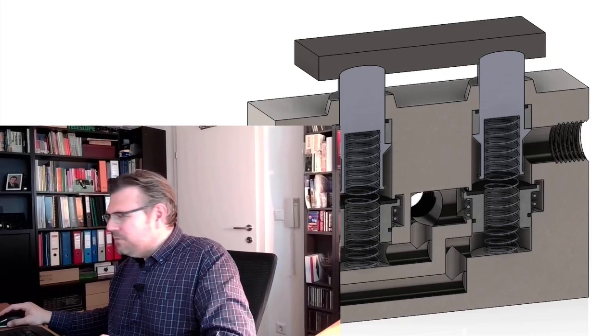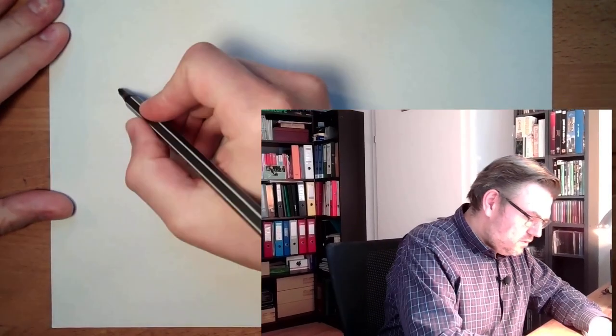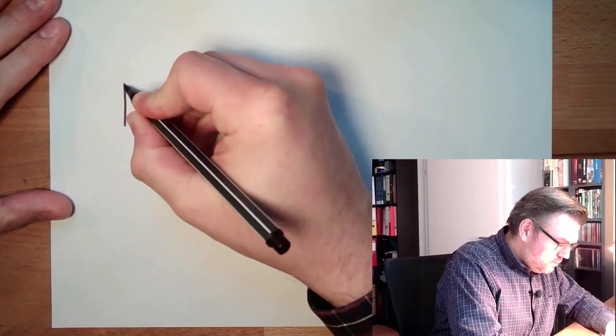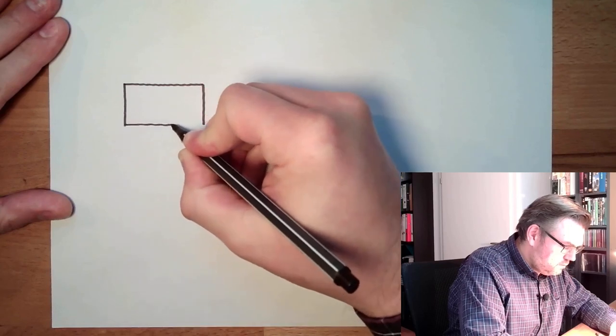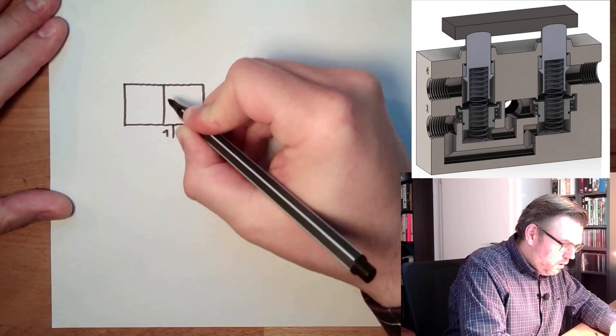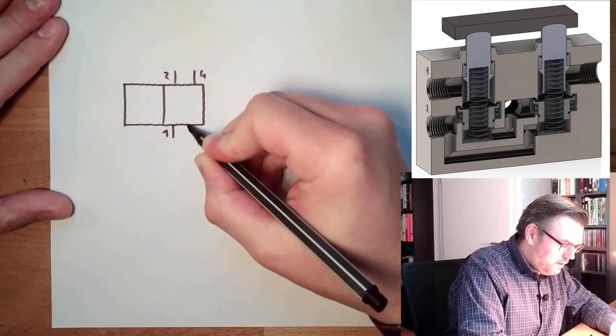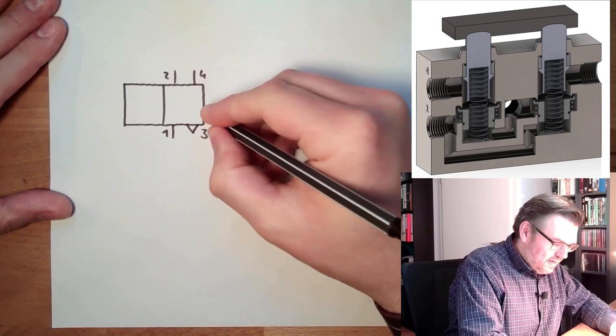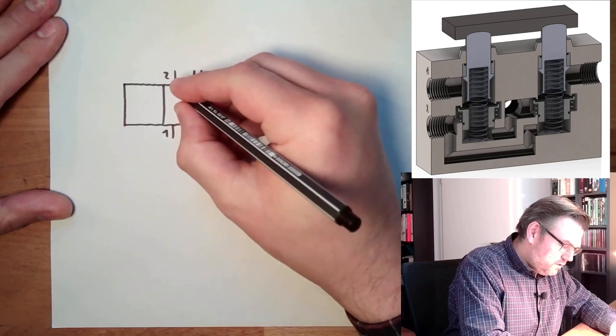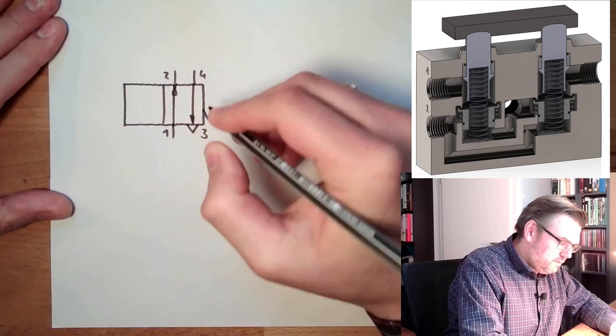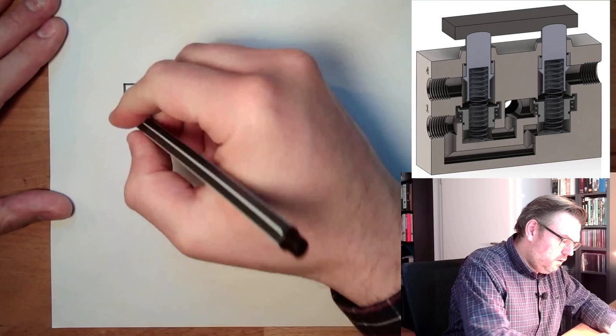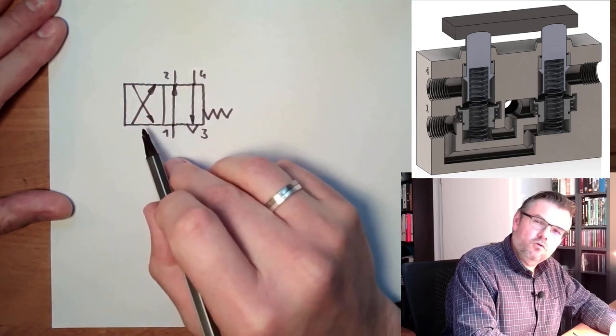Since we've always done this up to now, we will also try to draw the symbol. This time we have a 4/2-way valve. So actually the symbol should look like this. Two positions. There is the one connector, the two connector, the three connector, and the four connector. On this side we are spring loaded. In the rest position one is connected to two and four is connected to three. In the other position, one was connected to four and two was connected to three. So this is the straight position, this is the so-called crossed position.